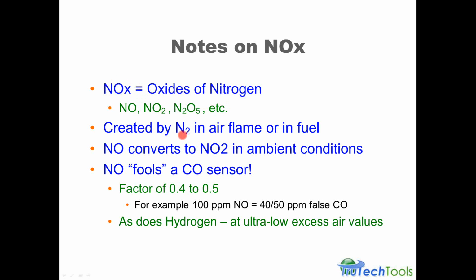Again, we mentioned created by nitrogen that comes through in the air, in the flame, or it's produced in the flame, or comes through in the fuel. And then the nitric oxide tends to be the highest concentration, the NO gas. It does convert to NO2 when it goes into the air, and it takes about 30 to 40 minutes for it to dissipate and to change over into NO2. However, when it's in the form of NO, and you're measuring especially in a flue, it is the highest concentration of all these species, usually about 80 to 95% is NO.